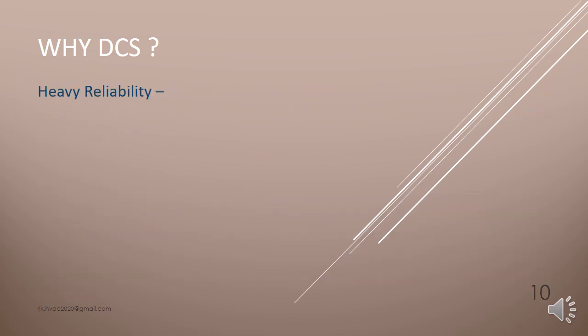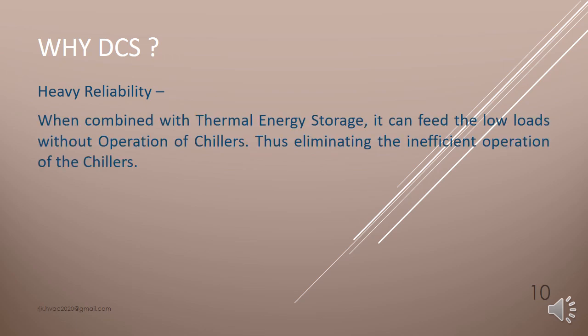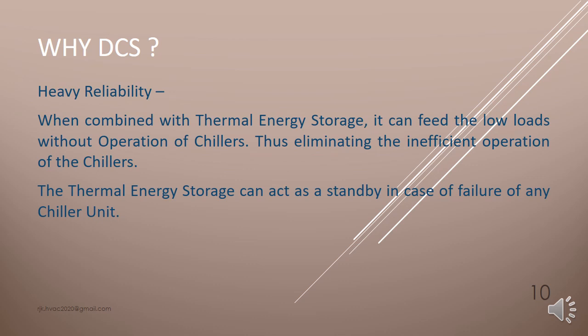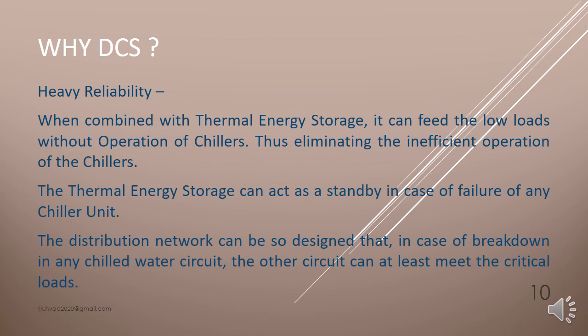Why DCS? Heavy reliability. When combined with thermal energy storage, it can feed the low loads without operation of the chillers, thus eliminating the inefficient operation of the chillers. The thermal energy storage can act as a standby in case of failure of any chiller unit. The distribution network can be so designed that in case of breakdown in any chill water circuit, the other circuit can at least meet the critical loads.